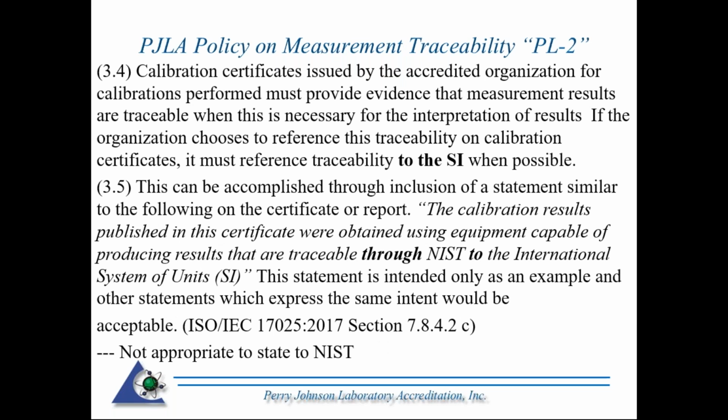So again, with SI, we keep hearing that term. When you are receiving a traceable calibration, or if you're providing them, make sure that you're providing evidence that measurements are traceable to the SI, and you should reference that. If the organization chooses to reference this traceability on calibration certificates, it must reference it to the SI when possible. So we do address this in P-L-2.